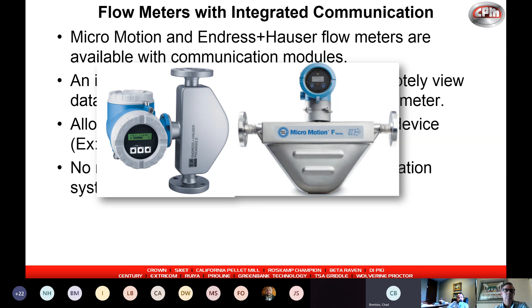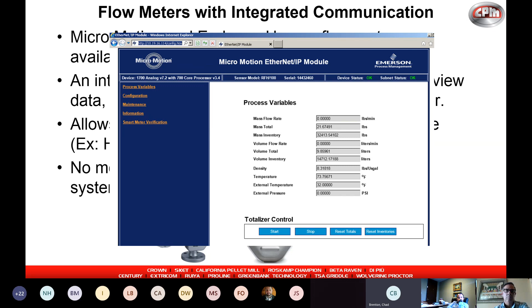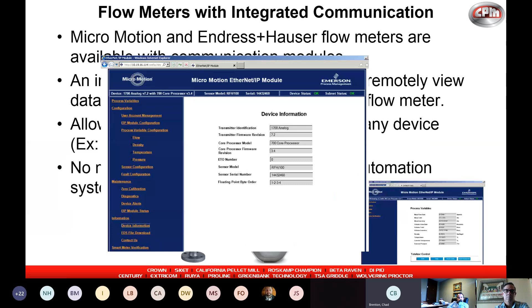Integration with a flow meter is an easy example. It eliminates the need for bucket tests, that's the biggest thing, because we can get the actual flow rate directly from the Ethernet signal instead of a pulse signal like we typically use, then verify it against a bucket scale. But it doesn't just give you the flow rate, we can also get the temperature, the density, and the volume going through that same device. Where we used to only get one piece of information, now we can get anything that flow meter provides.